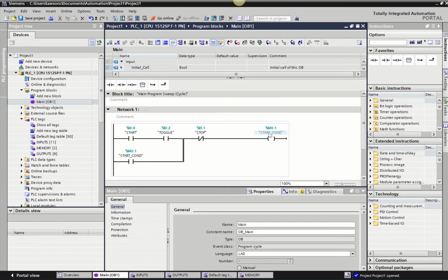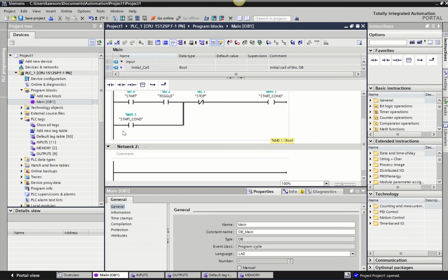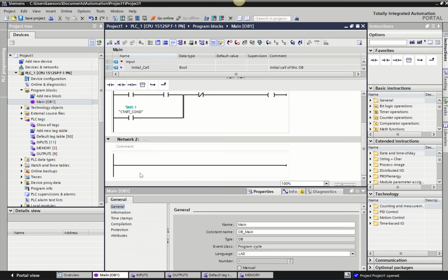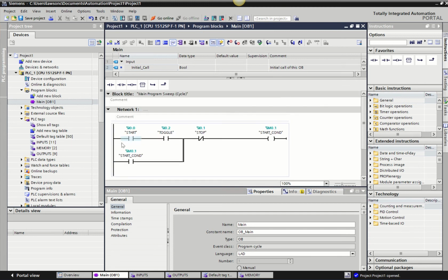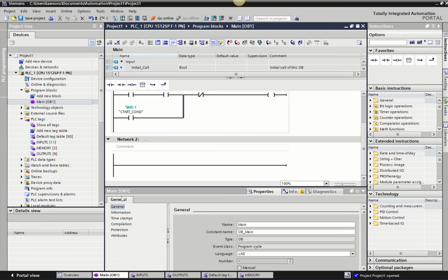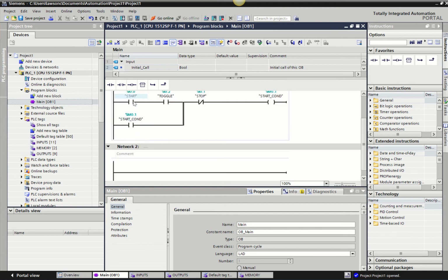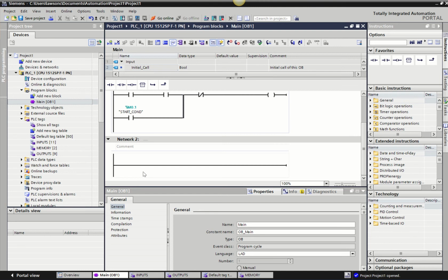Now what that is done by setting up that as a memory input, I can use that memory input then just to trigger to say yes, we've reached our start point, we're ready to rock, and we can trigger other statements further down. What this piece of control does give us is, if we needed to change the start condition, say we need to add in more inputs or add in different scenarios to get that to turn on, we only need to change it in one place, and then everywhere else I've referred to a start condition as an input to trigger it will automatically update. Whereas if I didn't have this, if I just use these two sequences, then every line that I needed to put in a start condition would ultimately need to be edited. So maybe you've picked up on that, and we'll see it in action here as we go.